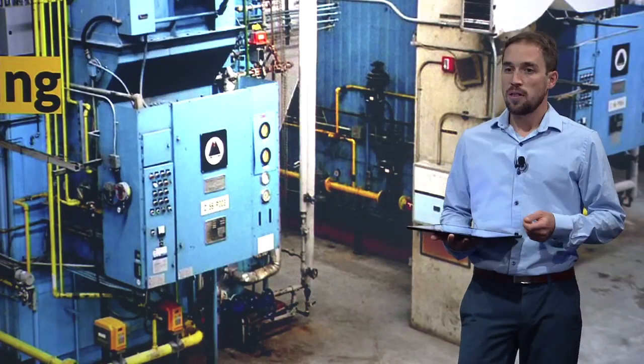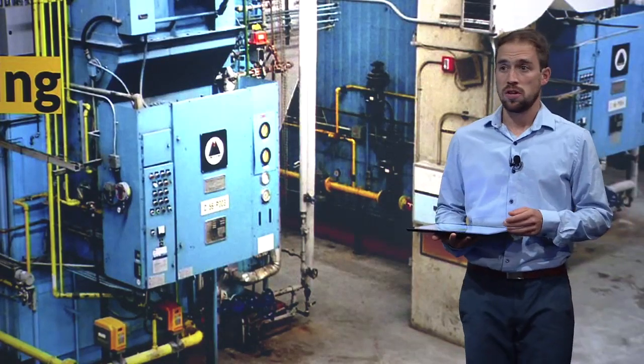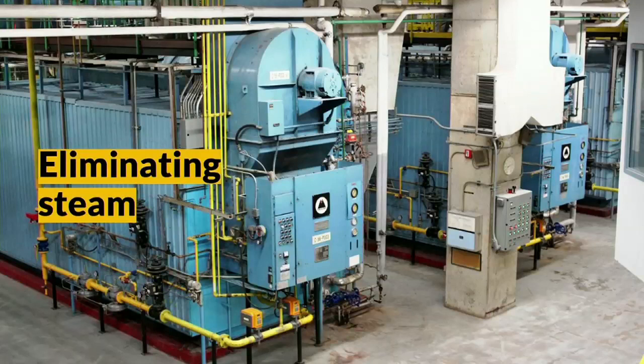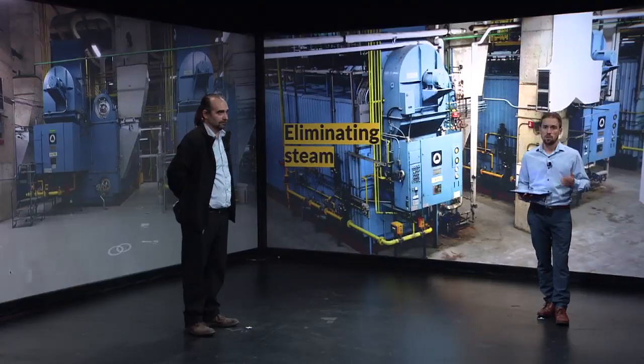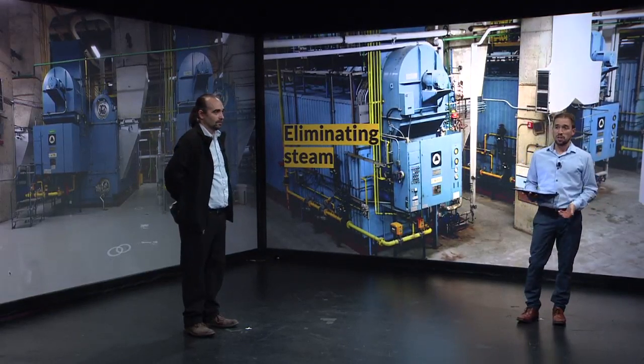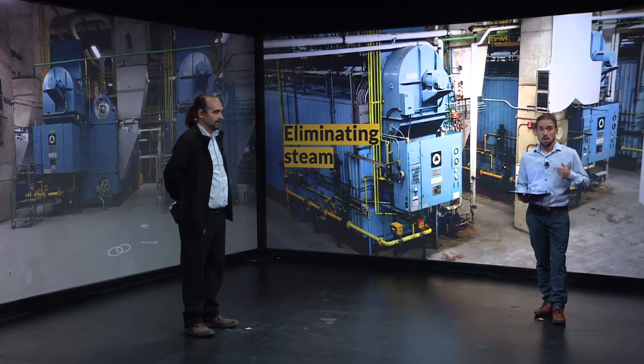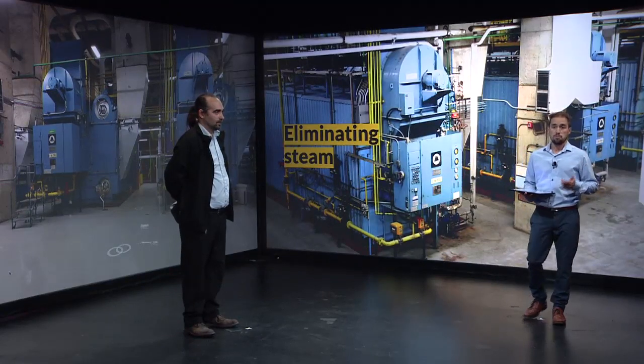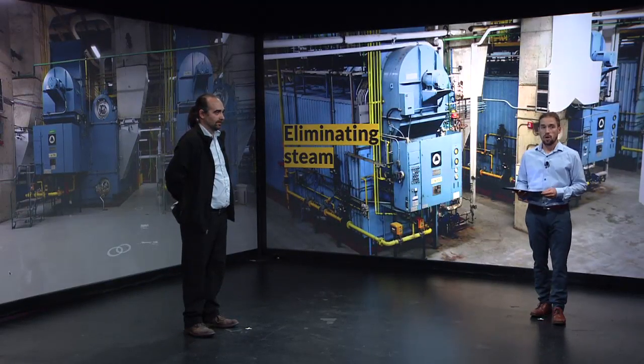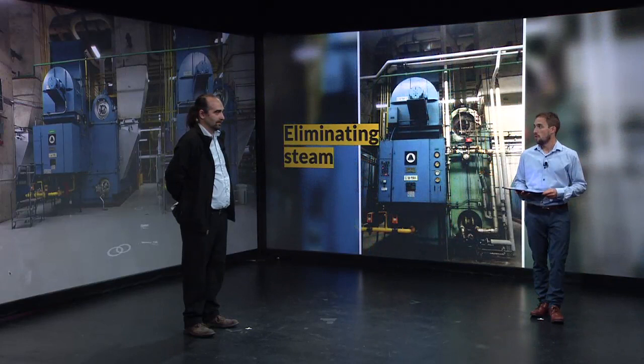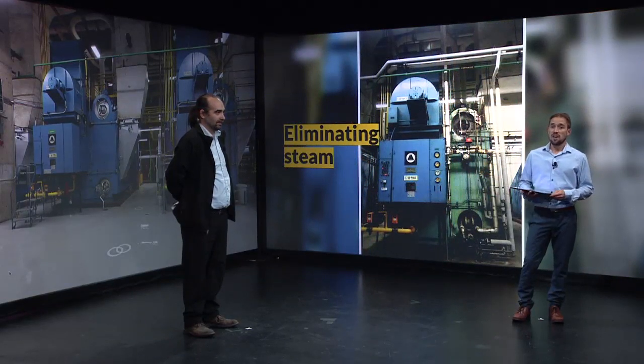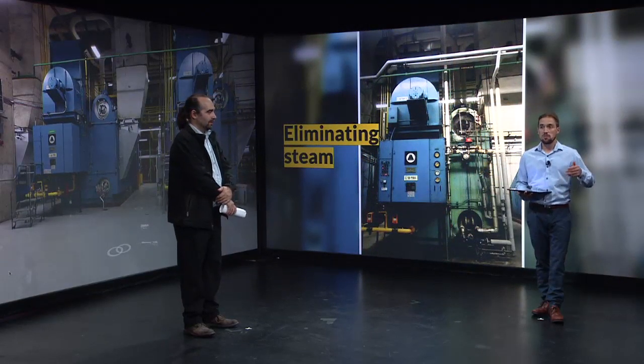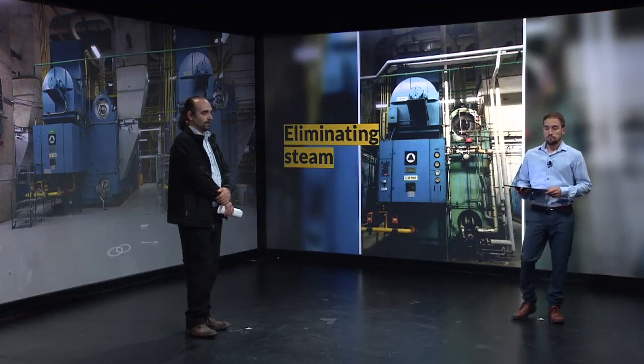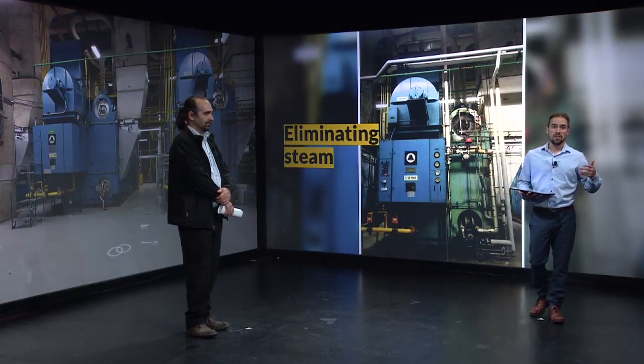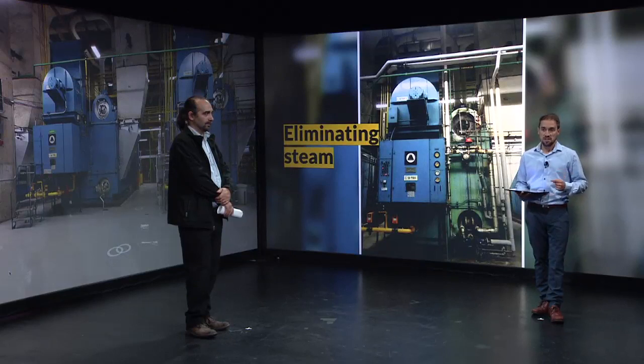Prior to that, we ran some tests to make sure they were in good condition. We looked at the tube thickness and things like that, to make sure they would last at least 20 to 25 years. Since they were really good quality boilers, pretty much way better than what we can find in new commercial boilers right now, we decided to reuse them and update them so they could make hot water instead of steam.